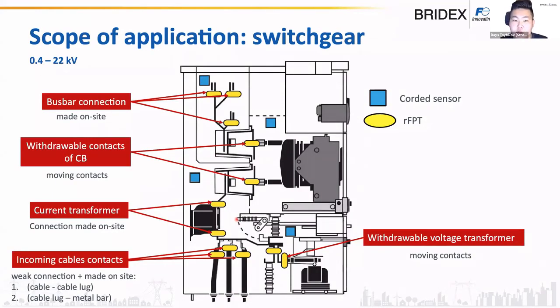Where should FIPRES be used? Let's start with the switchgear. It's one of the obvious examples, because the switchgear is very expensive, and it's a very important part of the electrical supply. Here we recommend installing the RFPT on the bus bar connections, because these connections are made on site. There's a big chance that such a connection gets loosened with time. For sure on the contacts of the circuit breaker, because it's withdrawable. Every time you put it out and put it in, the contact gets worse and worse.